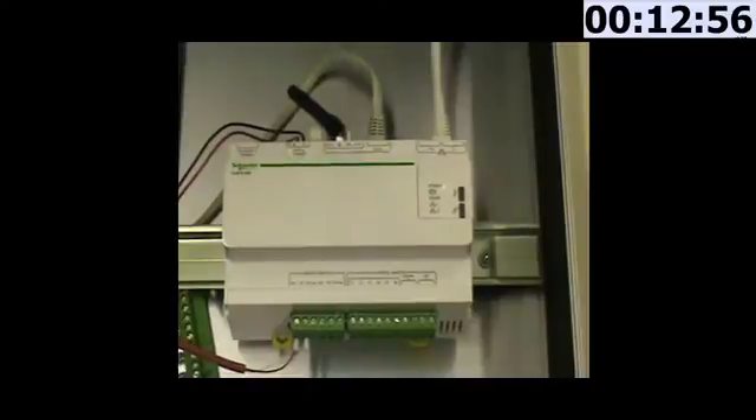Once you have added all the devices connected to your COMEX, you can go to the measurements table. From this table, you can have a synthesis of all the real-time measurements coming from the devices. After that, you would go to the commissioning page. From here at the top, you have notifications and you should see that your system configuration is okay. You can then enable the data logging, send the topology to your publication platform, and so on. You have then finalized the commissioning of your COMEX.